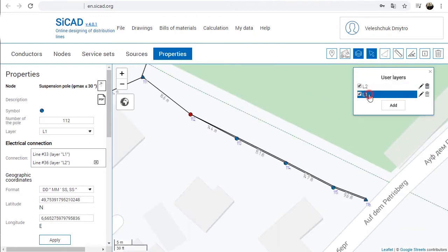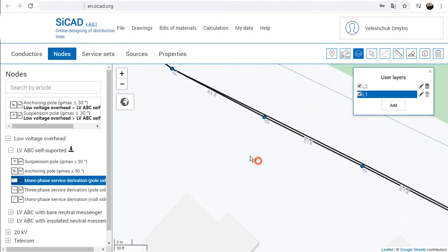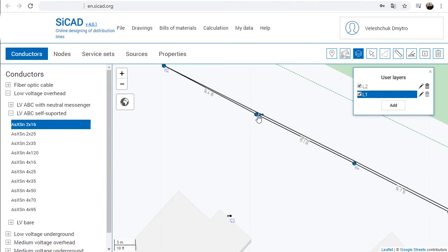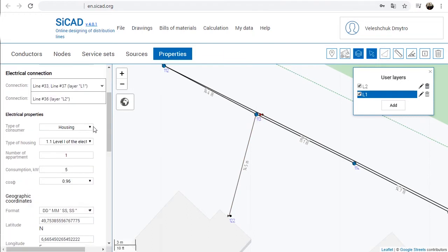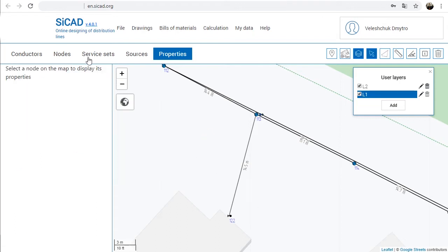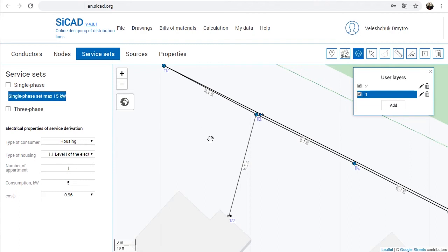To create a service derivation node, the following steps are to be done: select and place the pole side service node on the pole; select and place the wall side service node at the entry point of the building; select the service conductor and connect the appropriate pole side node group to the wall node on the building. Pole side service derivation nodes have parameters of electrical consumption in their properties, and they are used in the electrical calculations of LV networks. Select the consumption parameters for all pole side service nodes placed on the map. Service sets include a typical node on the pole side, a typical node on the wall side, and the conductor.